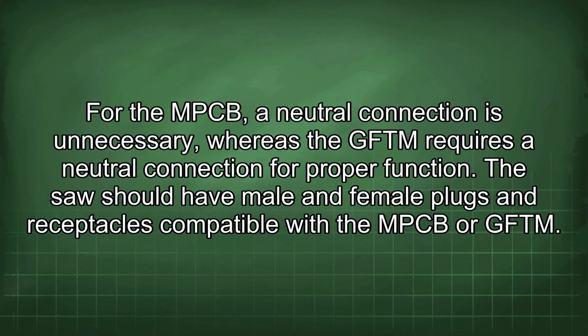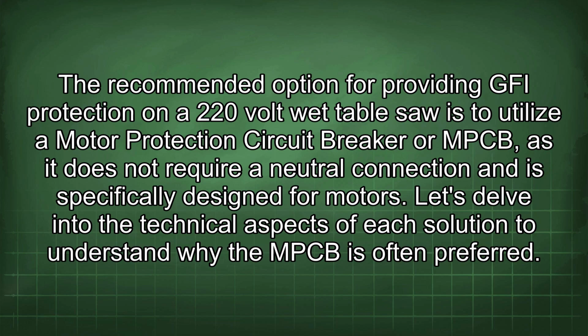For the MPCB, a neutral connection is unnecessary, whereas the GFTM requires a neutral connection for proper function. The saw should have male and female plugs and receptacles compatible with the MPCB or GFTM. The recommended option for providing GFI protection on a 220-volt wet table saw is to utilize a motor protection circuit breaker, or MPCB, as it does not require a neutral connection and is specifically designed for motors.